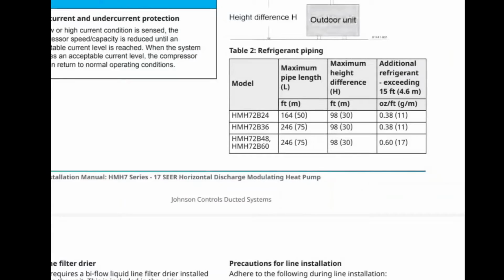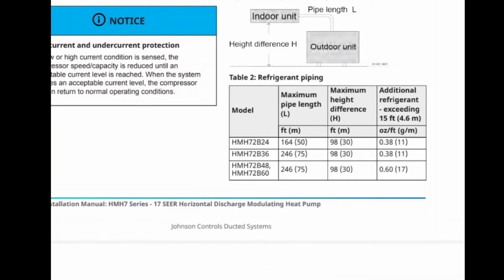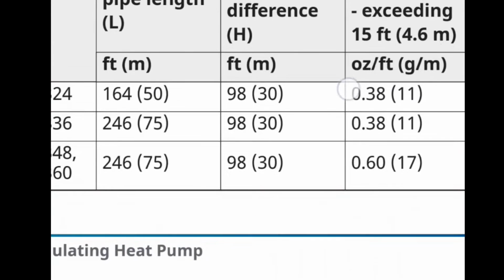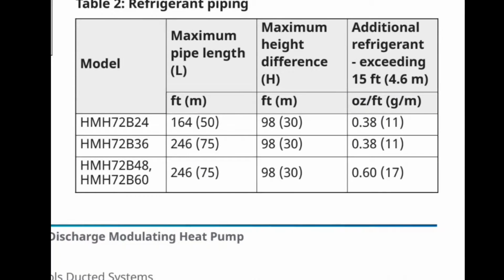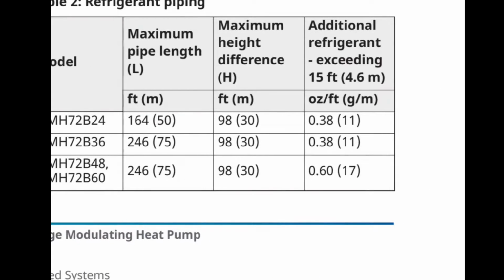Now let's charge it. This unit right here comes pre-charged for 15 foot of line set. We've got 80 foot, so we're going to add an additional charge, and for every foot, we're going to add 0.60 ounces. I'm going to show you that in the manual. For charging the HMH7, anything after 15 foot, I'm going to use this chart here. You got the model number on the left, very bottom, HMH72B60, because this is a 5-ton unit. And then over at the very right-hand corner is 0.60.